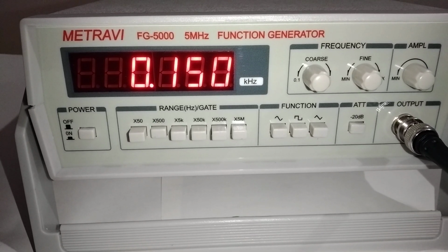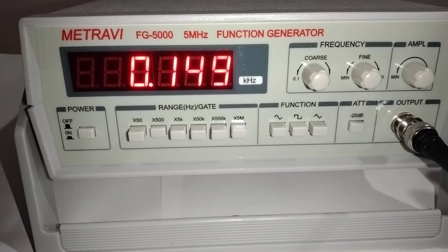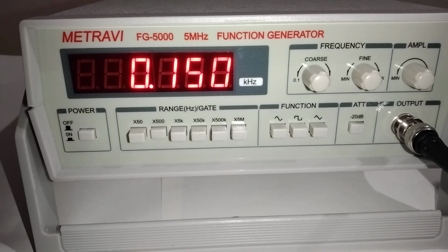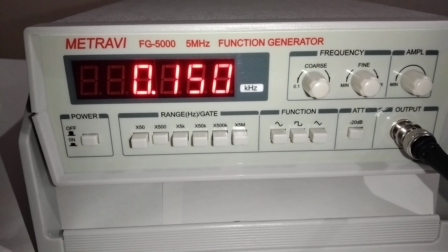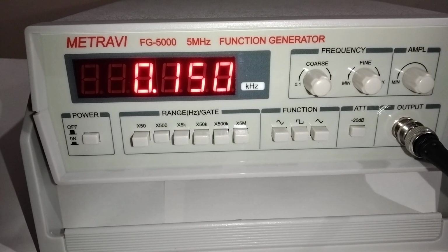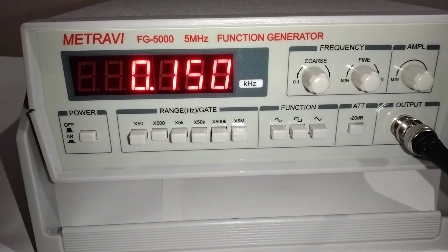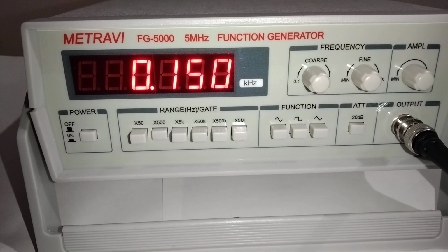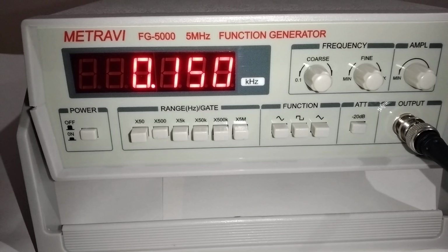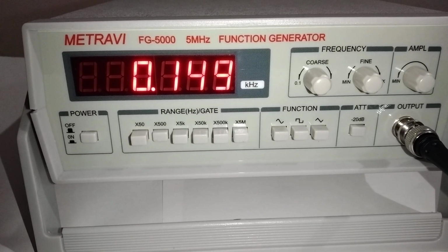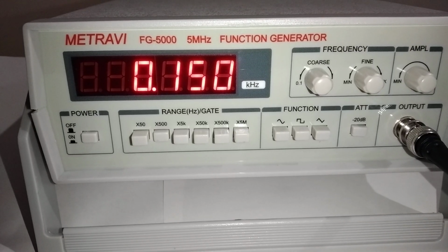In simplistic language, if 100 hertz is the frequency adjusted over here, then there might be a possibility that it may be 98 or it may be 102. So likewise you can calculate that 2% is for 20 hertz to 20 kilohertz, but as frequency increases above 20 kilohertz, the error may be up to 2 to 3%.